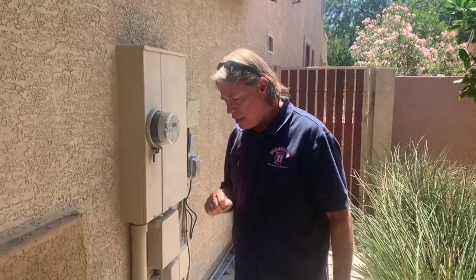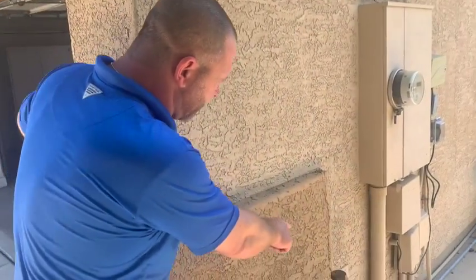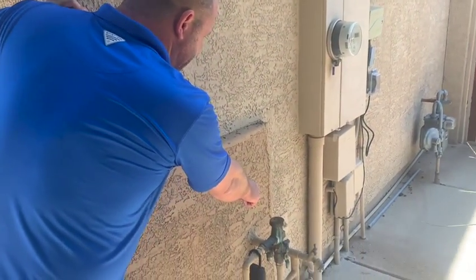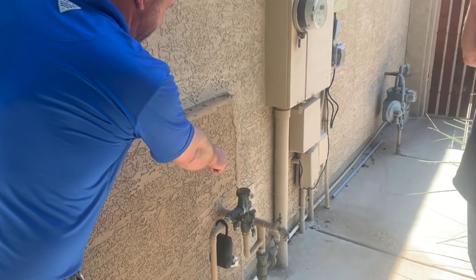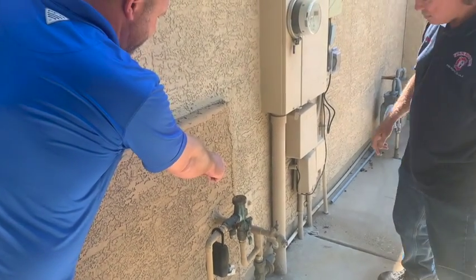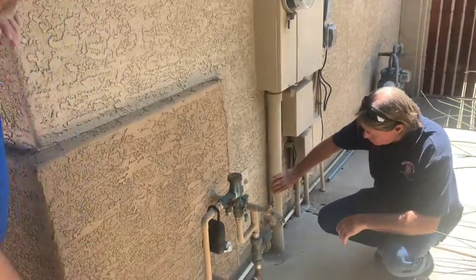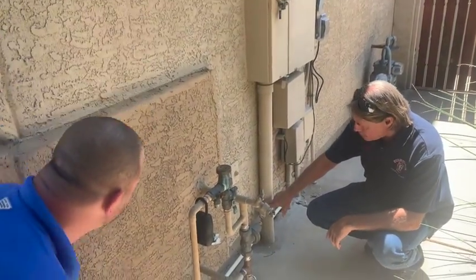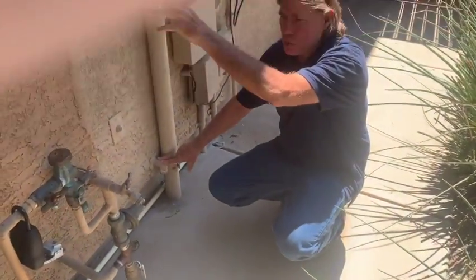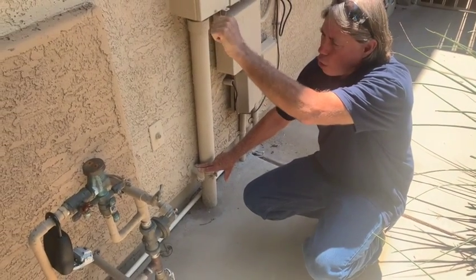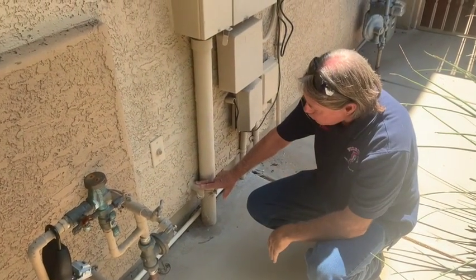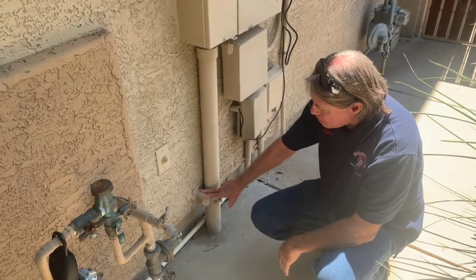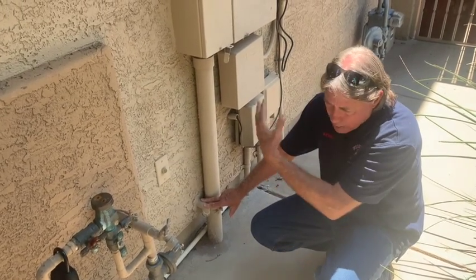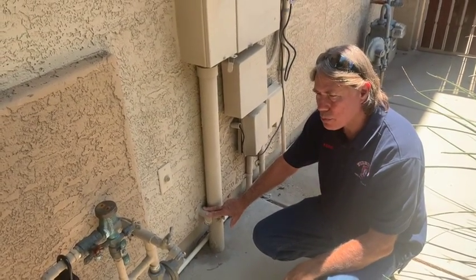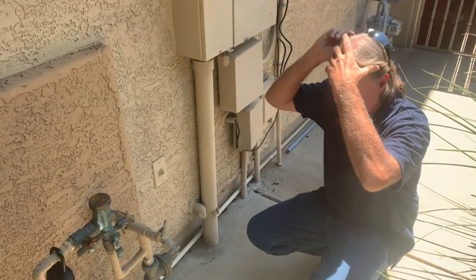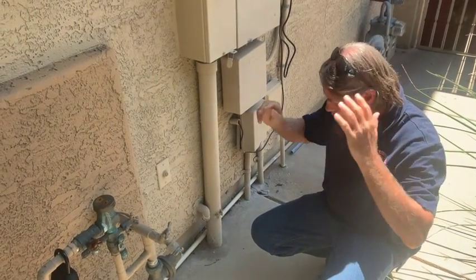One more thing that we have on the outside that's part of the system is this little kick-out plastic 90-degree PVC. And what's that for? Well, this is your drain. It's the main drain that we'll see here in just a second. You can open up that main drain and the water's going to flow out here. It's there for maintenance and to keep the water outside the house when we're doing any draining or maintenance. Excellent. So we should never see this one dripping at all. It should not be dripping.